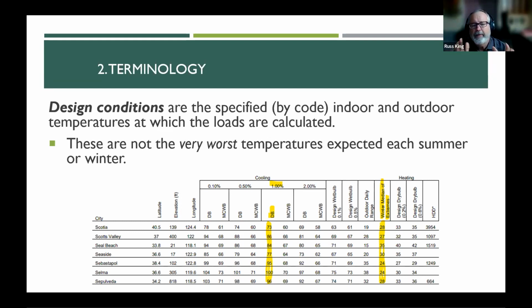So don't fall into the trap. HVAC contractors do this all the time. And they'll say, oh, your design temperature is 95, but gosh, that seems kind of low to me. I think we should design your system for 100 degrees. Don't fall into that trap. It's not allowed by code, for one thing. And it's just a way for them to justify putting in bigger equipment. Okay, so be careful of that. Then on the heating side, we use a number called the winter median of extremes. And in Sebastopol, that's a chilly 24 degrees is what we design to in Sebastopol. Okay, so those are required by code. And don't stress over those numbers. They're very well-proven numbers.